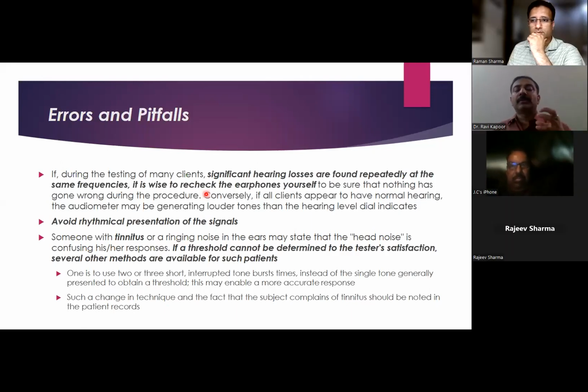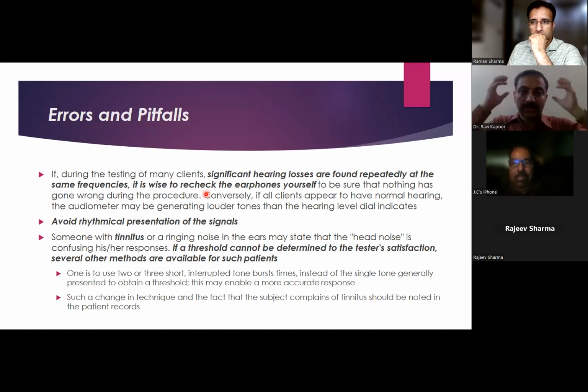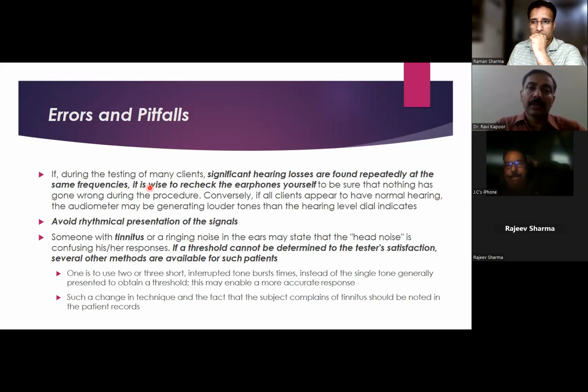We need to give some frequent checks on our own self. We can place the earphones on our own ears and then present the tones to right and left ears at soft intensities to check whether we are handling a correctly working audiometer.